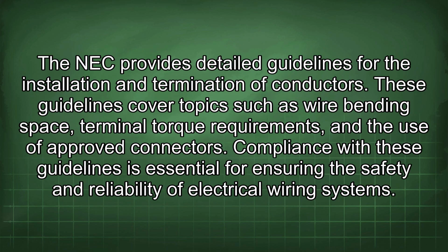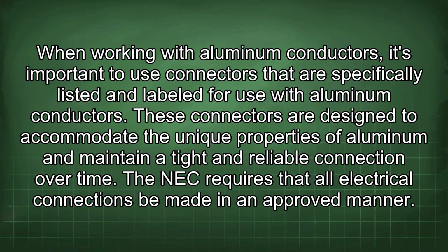The NEC provides detailed guidelines for the installation and termination of conductors. These guidelines cover topics such as wire bending space, terminal torque requirements, and the use of approved connectors. Compliance with these guidelines is essential for ensuring the safety and reliability of electrical wiring systems. When working with aluminum conductors, it's important to use connectors that are specifically listed and labeled for use with aluminum conductors. These connectors are designed to accommodate the unique properties of aluminum and maintain a tight and reliable connection over time. The NEC requires that all electrical connections be made in an approved manner.